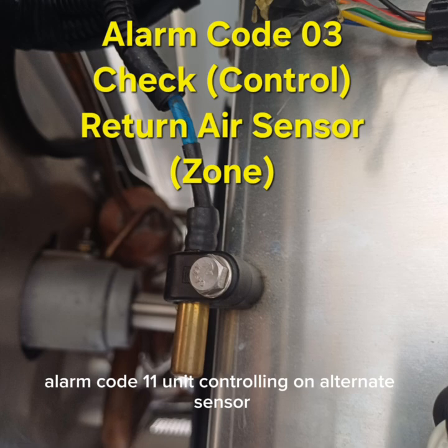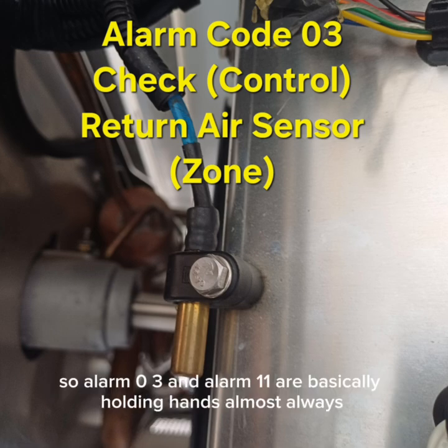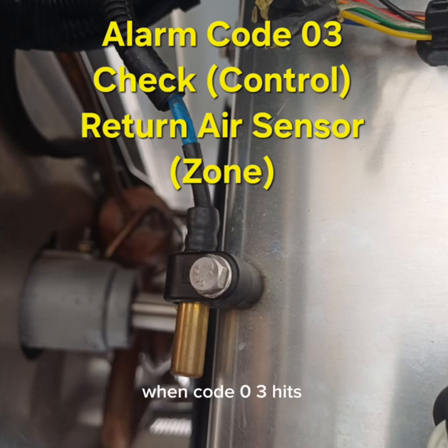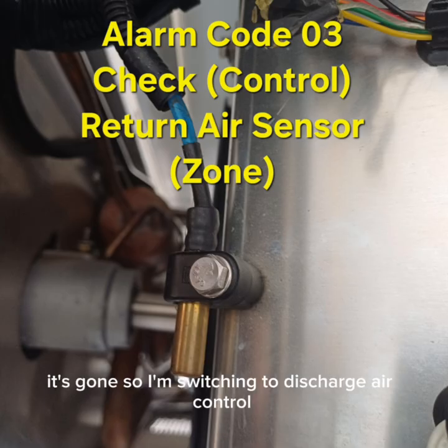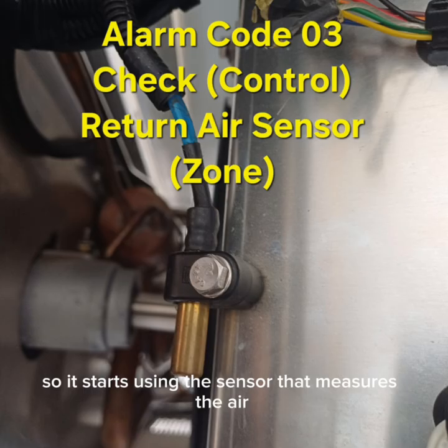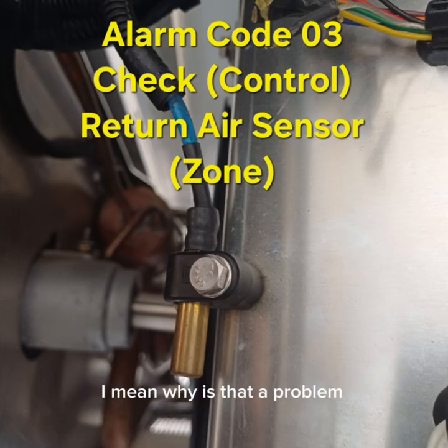Alarm code 11, unit controlling on alternate sensor. I see that in the troubleshooting tree here. So alarm 03 and alarm 11 are basically holding hands. Almost always. When code 03 hits, the unit effectively says, I can't trust the return air anymore. It's gone. So I'm switching to discharge air control. So it starts using the sensor that measures the air leaving the unit instead. Precisely. That sounds like a reasonable backup plan. I mean, why is that a problem?